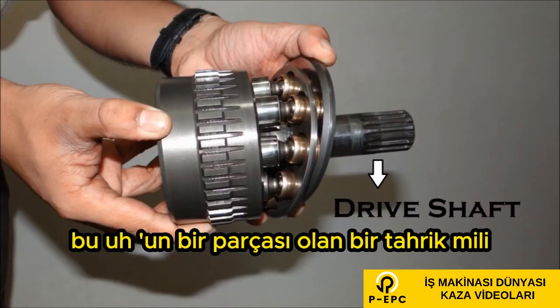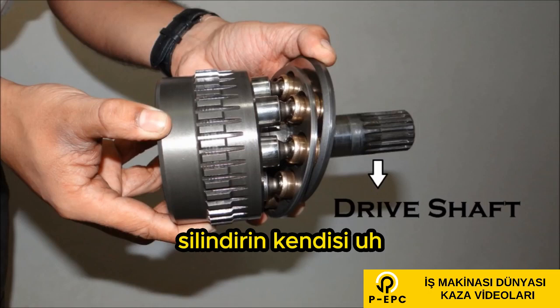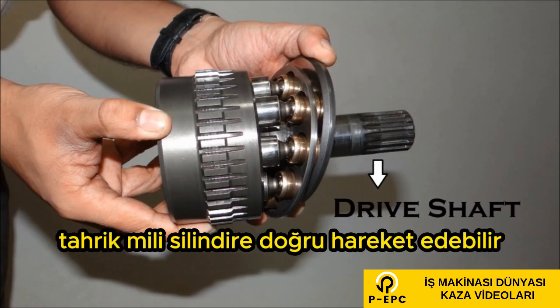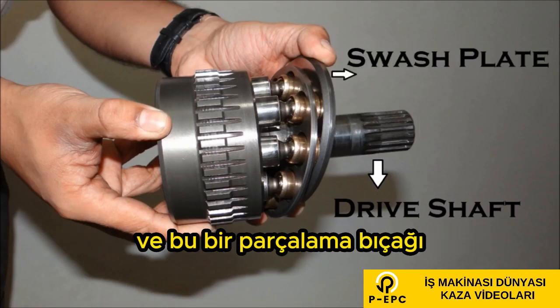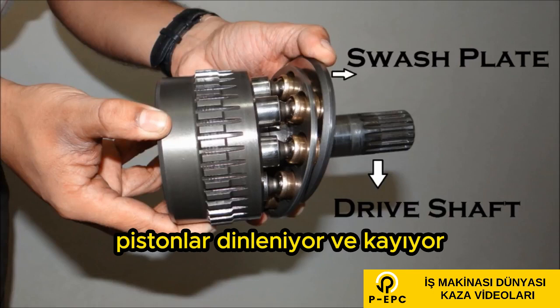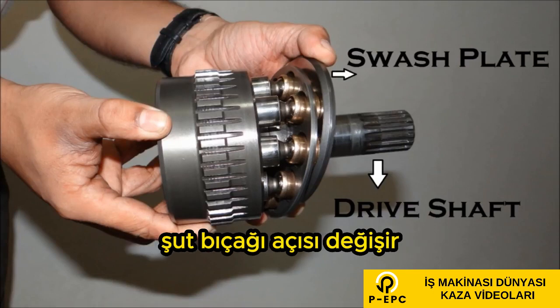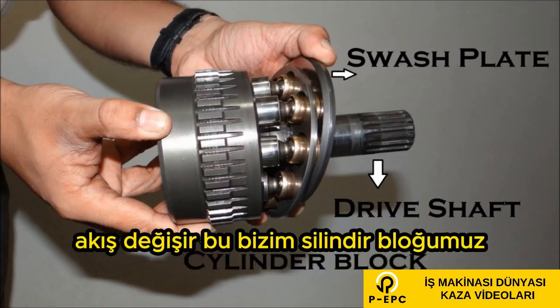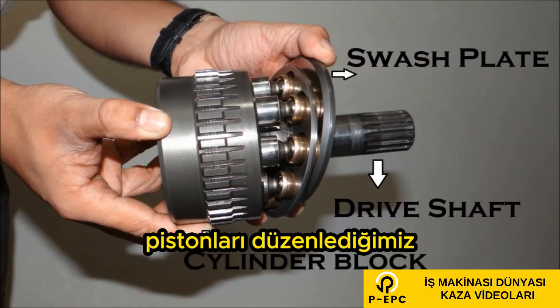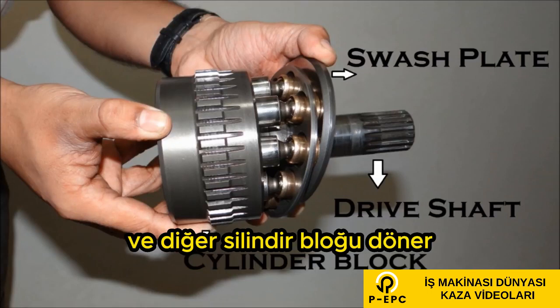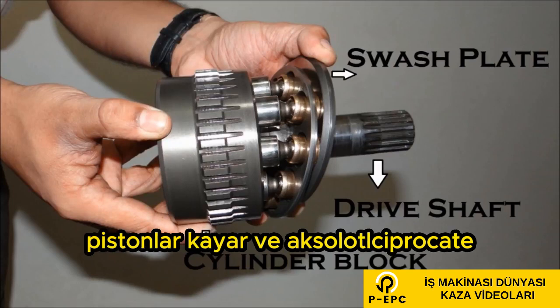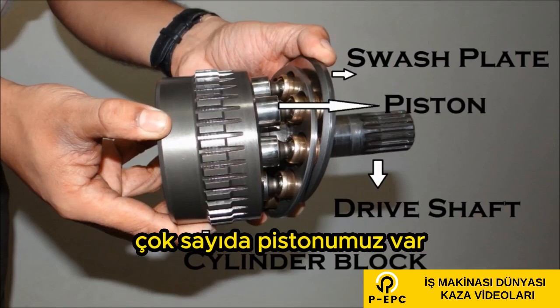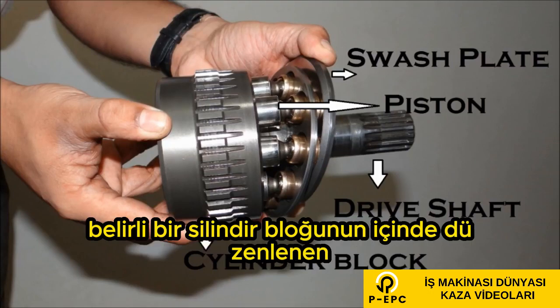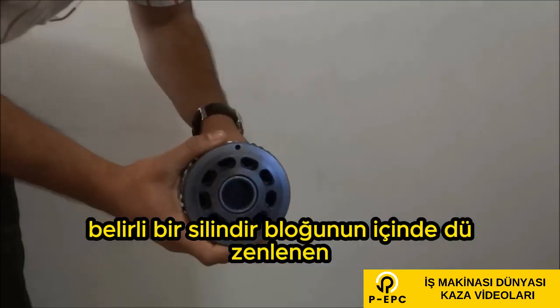That's the drive shaft, which is a part of the cylinder itself. The drive shaft gives drive towards the cylinder, and that's the swash plate, which I told the pistons are resting and sliding over. The swash plate angle changes, the flow varies. That's our cylinder block in which we have the pistons arranged, and as the cylinder block rotates, the pistons slide over and actually reciprocate. That's the pistons over there. We have many pistons arranged inside a particular cylinder block.